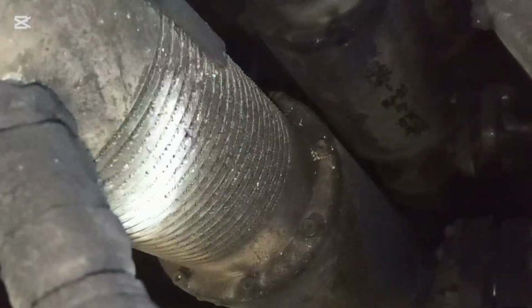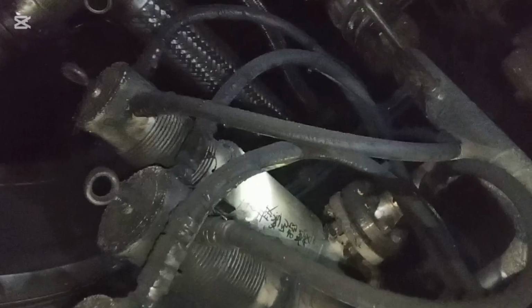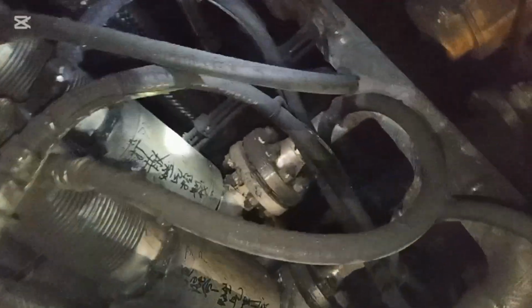Inside the gas control valve chamber we checked that all the connections, the electrical cable connection, the instrument cable connection as well as the mechanical pipe connection, are okay, but there is some dust. Moreover, we checked and followed the line and saw that the line is properly okay. Here is the valve line. This is the connection line from this valve, the motor operated valve. From the motor drive controller, the output line is connected to the valve.